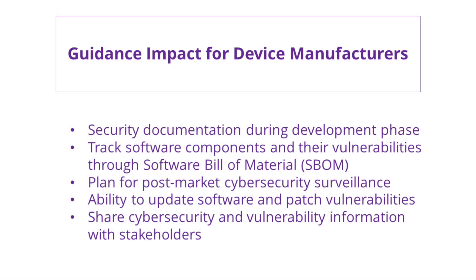What does this mean for device manufacturers? It means more emphasis on security documentation during the development phase, tracking software components and their vulnerabilities through software bill of materials, planning for post-market cybersecurity surveillance, and ensuring there is a way to update software and patch vulnerabilities.